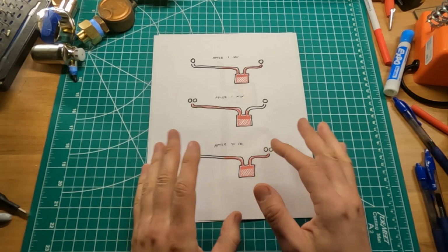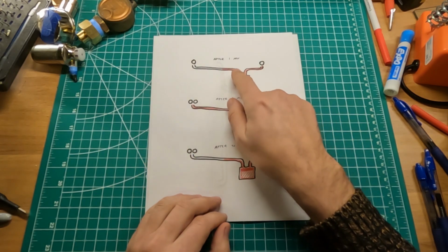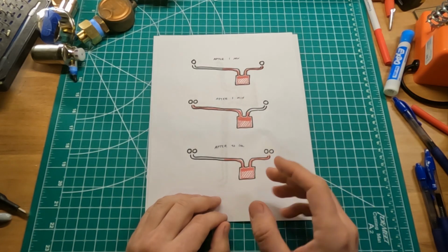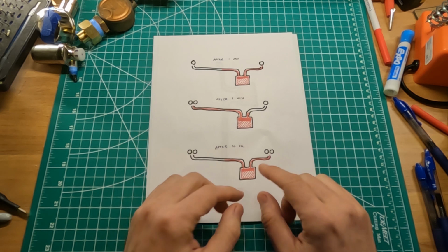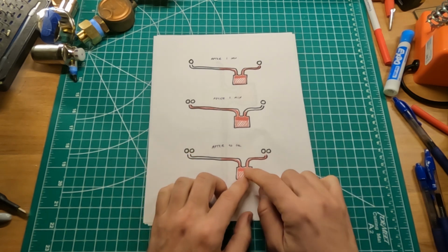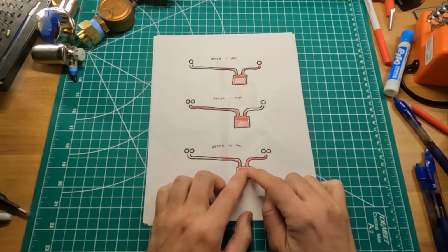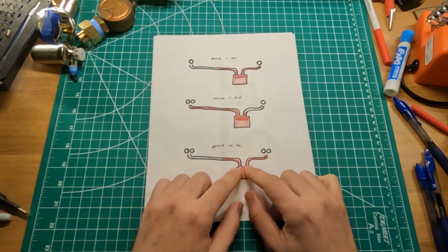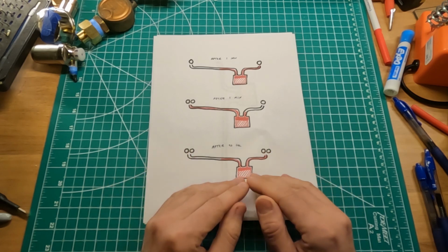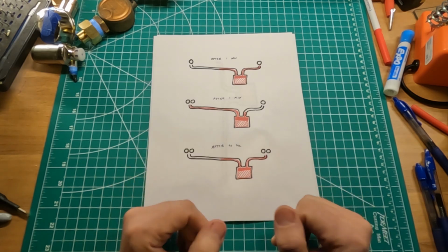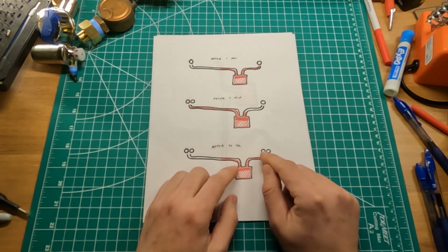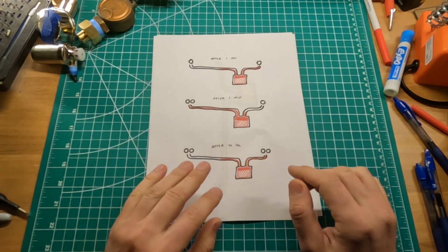So this is all relative. I put that this is the amount of steam you will get with 1 minute. This is the amount of steam we get in 30 seconds. That's not exactly true, because at least at the beginning of the boiler operation, there's a limited amount of steam happening. So you would still get the same equal distribution if you have the same venting on both sides, because it takes the same amount of force, the same amount of work, for the steam to go to either pipe and push out the air.